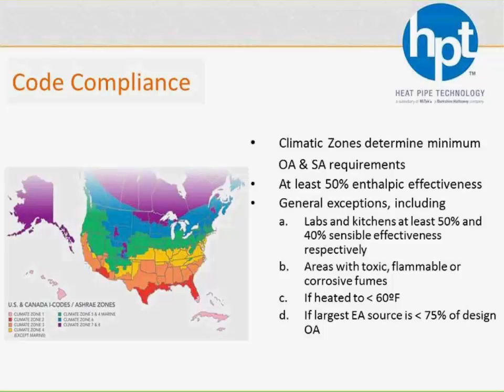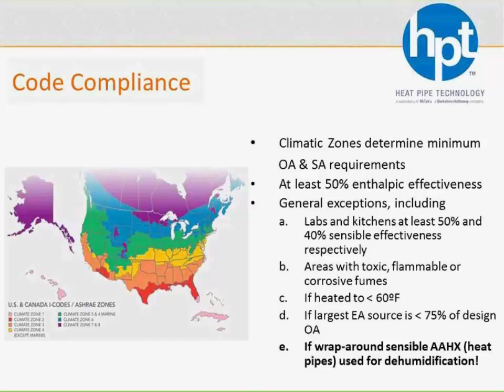There's also some exceptions to that rule. You know, labs, kitchens, they have their own exceptions, some other stuff, but the one I want to point out is that the last exception listed is that if a wraparound heat pipe is being used, now AHRI calls it in-series heat recovery, but that's because it's all happening within the same airstream as opposed to 2 separate airstreams. But if you're using in-series heat recovery or a wraparound heat pipe, then you have met code. You do not have to do anything else. So know that if you've got a DOAS unit, single path, with a wraparound heat pipe in it, and you put it in there to downsize your equipment and make it more efficient, you have met code. You do not have to do anything else from an energy recovery standpoint to meet code. It has now been met.